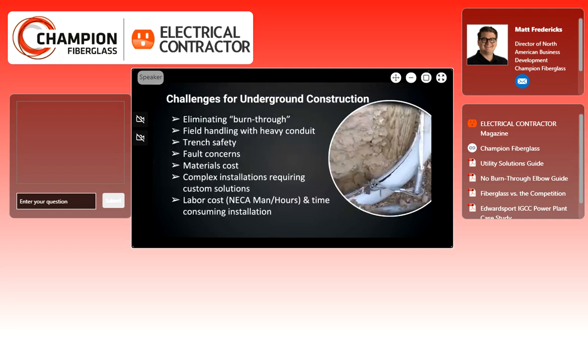So, challenges for underground construction. Many things to keep in mind. One that I would say is a common issue that folks have come into for many years now is dealing with burn through. What burn through is, it's actually illustrated in the picture on your screen right now. It's when a pull rope or a wire braided rope essentially gets too hot on the inside edge of a PVC elbow, and it can actually slice right through the inside edge of that elbow.